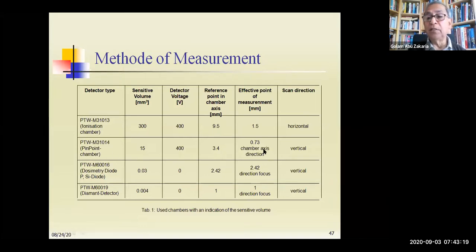When you use the pinpoint, the chamber should be vertical. Here is vertical. And this is sometimes very difficult. The chambers have some marking. Where can you find the effective point? But in the pinpoint chamber, we have no marking. So through these values, you should put it in the right position.